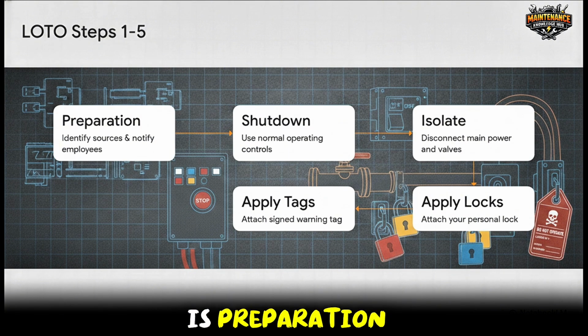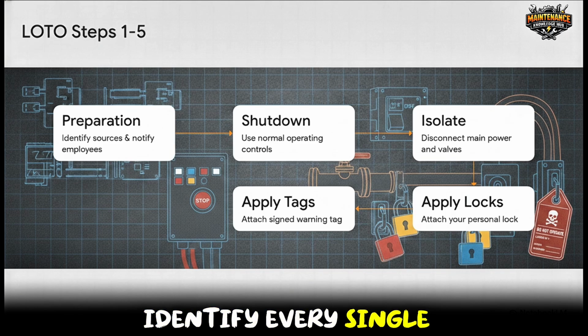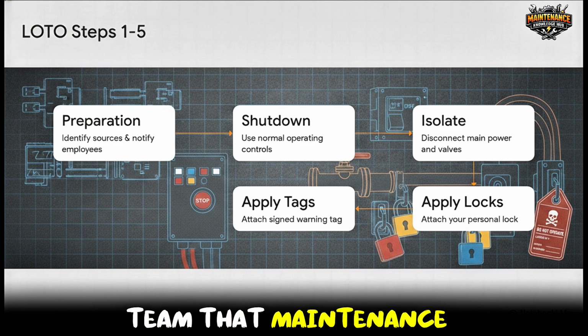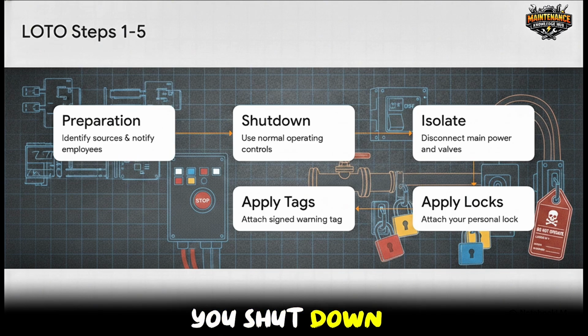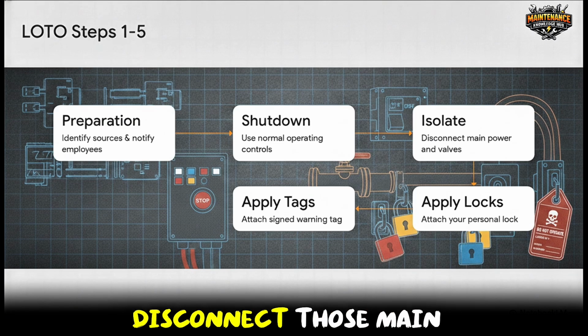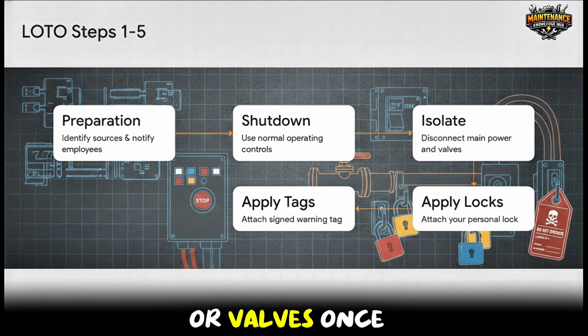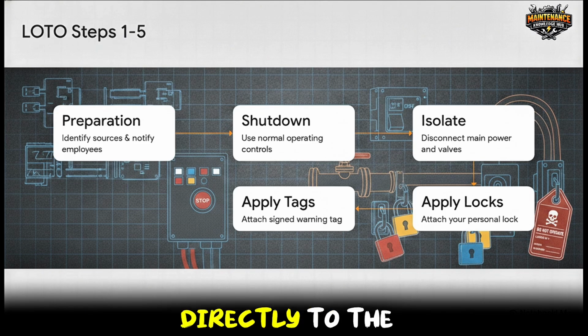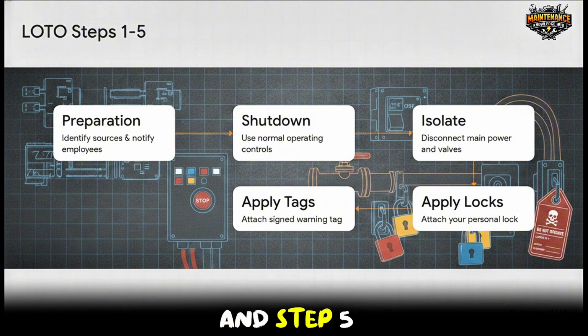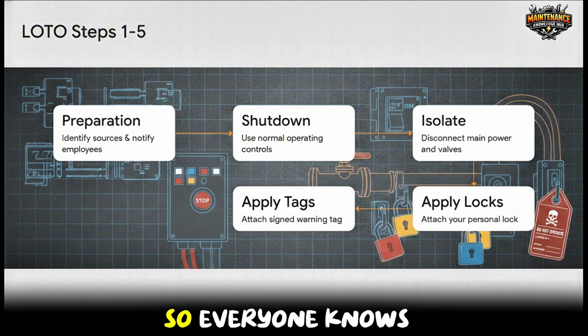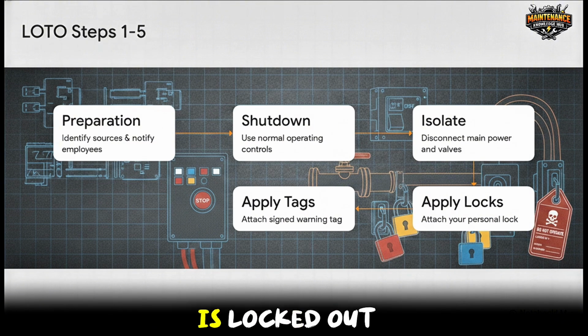Step 1 is preparation: you have to identify every single energy source and notify your team that maintenance is starting. Next, you shut down the machine using its normal controls. Step 3 is isolation, where you physically disconnect those main breakers or valves. Once that energy is severed, Step 4 is applying your personal lock directly to the isolation device. And Step 5, you attach your signed warning tag so everyone knows exactly why that equipment is locked out.